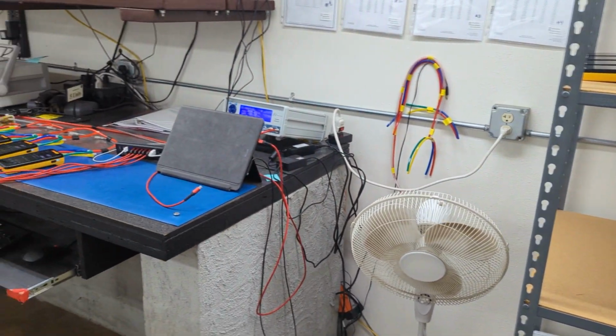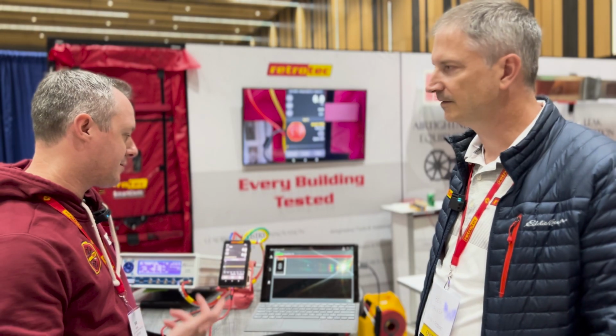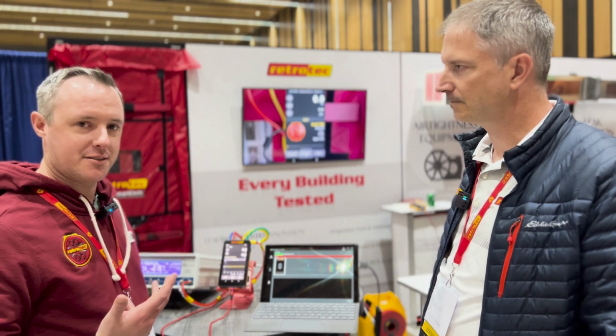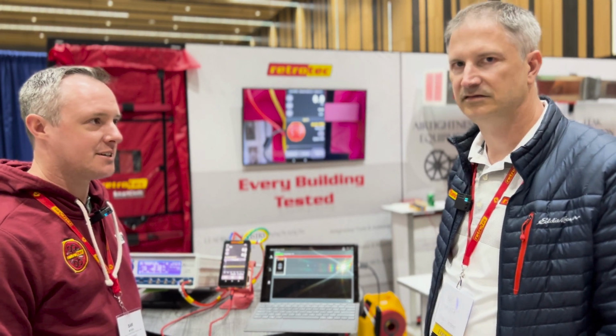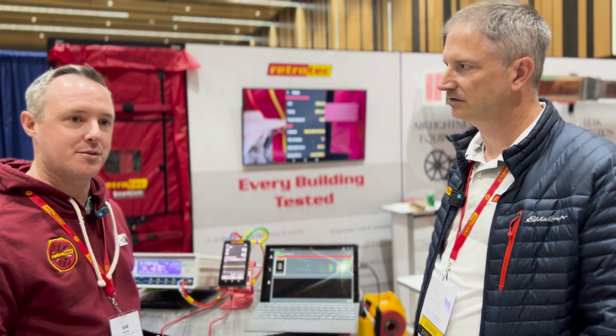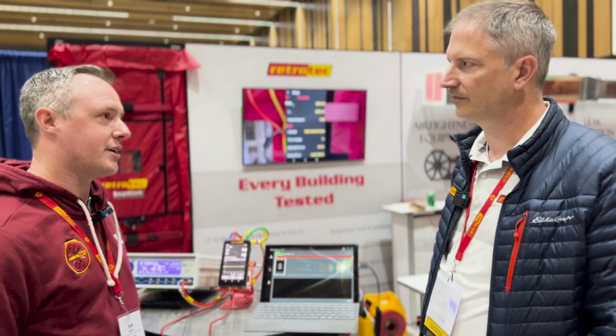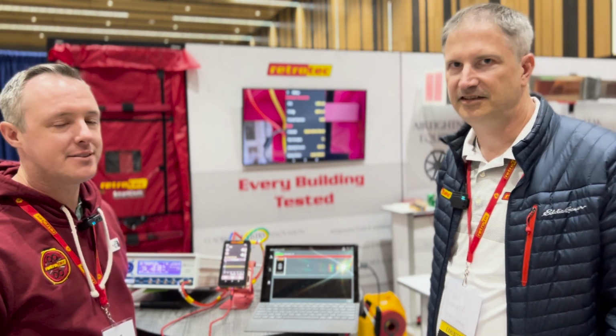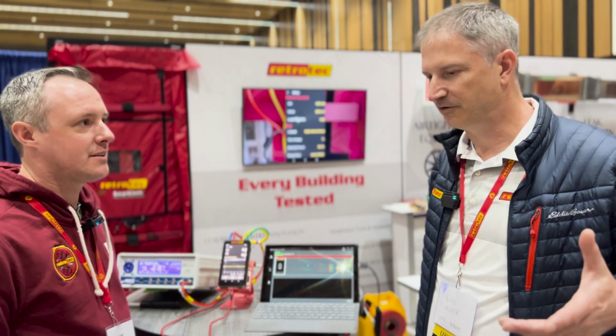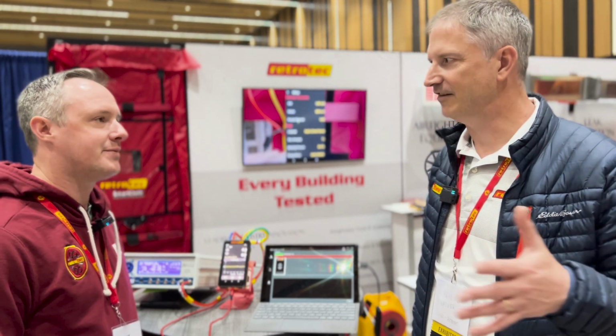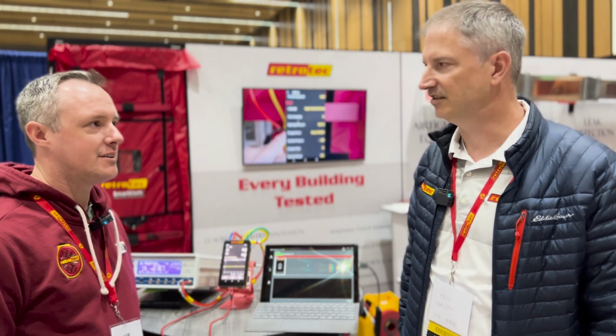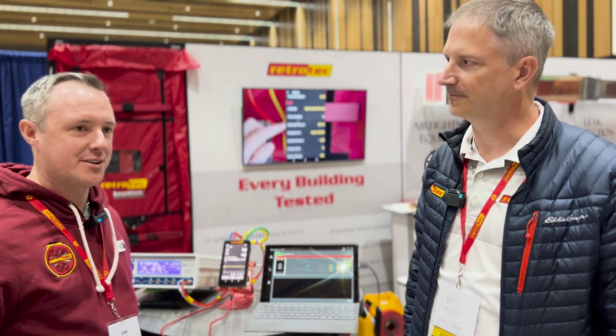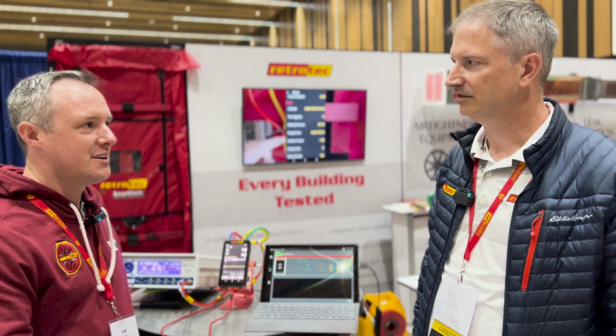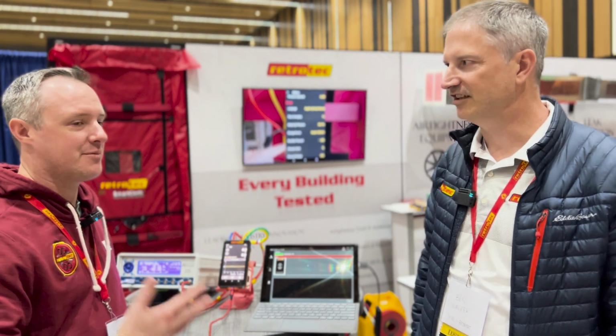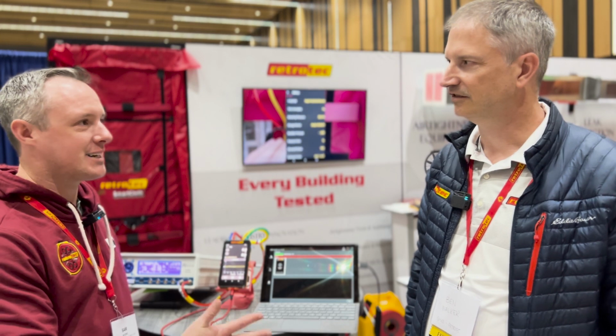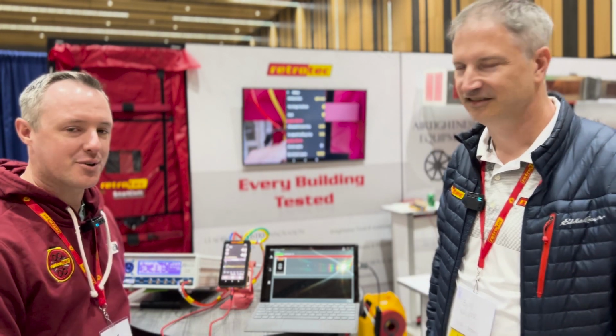Cool. Yeah. So our DM32 manometers and our new DM32X manometers, what we're recommending is 5 years for our calibration interval. Yeah. And if you're still using our older DM2s, it's still 2 years, but we're still calibrating those, right? Yeah, exactly. And it's also important to make sure that you're meeting the requirement of the standard that you're testing to, because they may have different interval requirements based on different standards around the world. So 5 years is our recommendation. Some standards say do whatever the manufacturer says, but some standards might say we don't care what the manufacturer says, we still want it done every year. So it's important to pay attention to that.